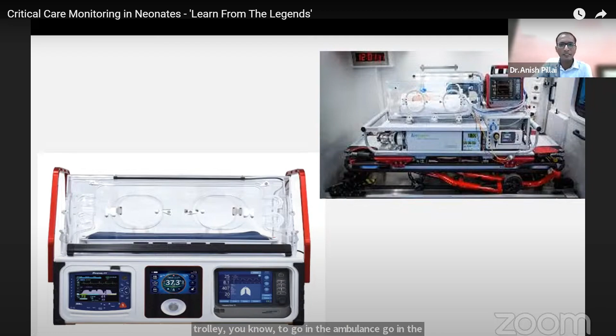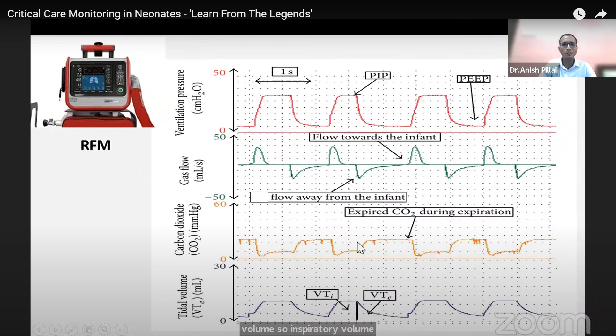This is how the displays work for the respiratory function monitor. As you can see, it is showing the pressure time scalar, PIP, PEEP, the total inspiratory time. It is showing the flow time scalar: the inspiratory flow, then there is a pause, then expiratory flow. Here again, inspiratory flow, then pause, then expiratory flow. It is showing the EtCO2. Obviously the CO2 is going up, which is the expired CO2, then it goes down. That graph also gives you an idea that the ET tube is in place. And the tidal volume: this is the volume time scalar, telling you the tidal volume. So inspiratory volume, and at the end of inspiration, you have this small expiratory tidal volume. These many parameters, or sometimes even more parameters, are available on display with good respiratory function monitors.